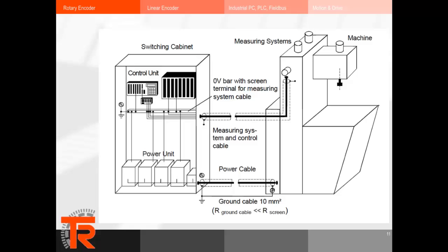We're looking at a basic diagram depicting grounding and shielding techniques as recommended by TR Electronic. You see the zero-volt bar with the screen terminal for measuring cable. Manufacturers such as Phoenix Contact and Wago make screen terminals, which are recommended and should be dedicated for sensitive measuring equipment. The shield is tied on the machine side as close to the measuring system as possible, and on the other side attached to the zero-volt bar. The resistance of the ground cable should be far less than the resistance of the cable screen, to make a more attractive path for electrical disturbances — we don't want that noise to travel across the encoder screen.